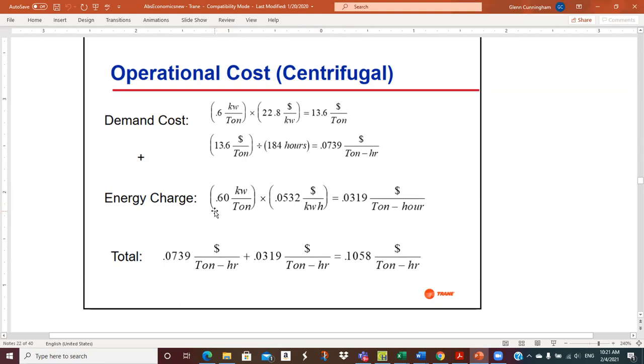And then the energy is a little more straightforward. It's just 0.6 kW per ton. And so if you ran that for 1 hour, or for 1 ton hour, so you're assuming 1 hour in here, 0.6 times the rate, 5.32 cents, gets us another 3.19 cents per ton hour. And so the total cost of operating this is demand plus energy. Add them together, you get 10.58 cents per ton hour.